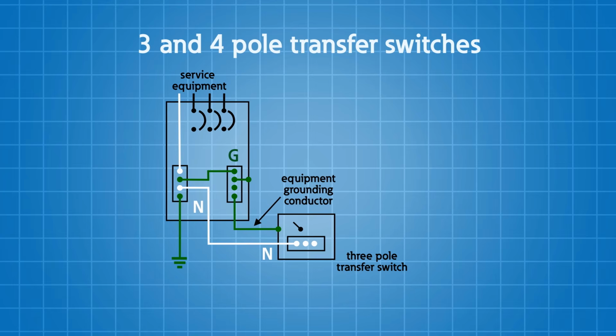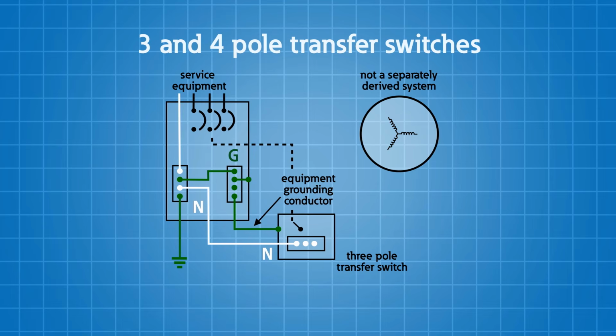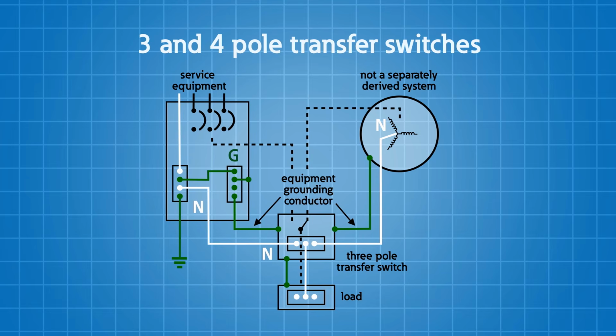You'll have a feeder come off of your panel board and feed the transfer switch. On the other side of that transfer switch, we have a generator. The generator will be connected directly to the transfer switch, obviously through some overcurrent protective devices, and then your transfer switch is going to supply loads. So this is a basic layout of a transfer switch with a generator in a system.